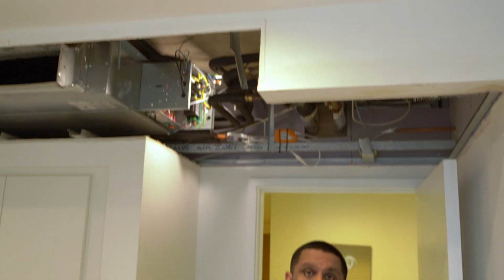Number two, unit heights. So the existing unit was smaller. The existing unit also sat higher. So we had to adjust the discharge plenum to make sure that the grill location, which remained fixed due to the ceiling height, lined up, and we were not affecting airflow in any negative way. It's all good getting things to fit, and it's all good getting things to work, but you have to maintain these things that you install. And these pieces of equipment need adjustment and regular servicing. So as you can imagine, with a larger fan coil unit, we had to take away a majority of the ceiling, and we have to come up with a way where we can provide access and get access to the filter so we can do the annual maintenance to ensure this unit works correctly.